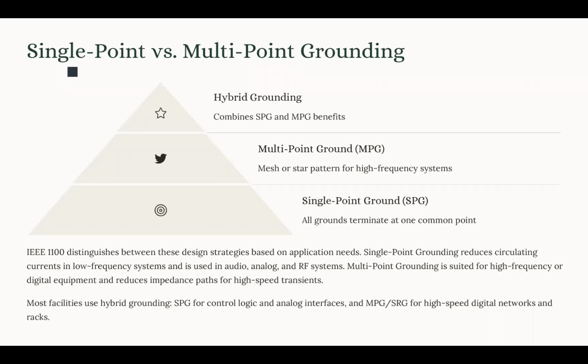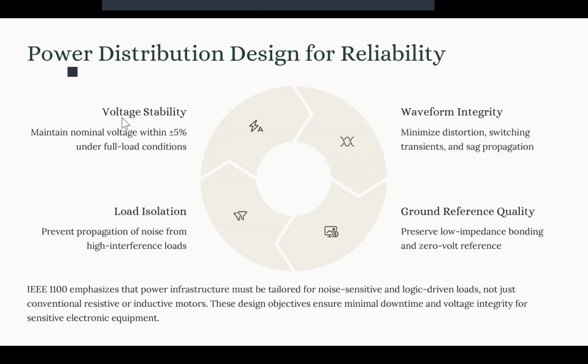Now that we talked about how we could connect all the grounding system to the building grounding, let's talk about the power distribution design defined in this IEEE 1100. Now, the objective of this design is to provide a clean, stable, and uninterrupted power for the sensitive electronic equipment. And it does that by minimizing the voltage fluctuations and waveform distortions and the noise propagation.